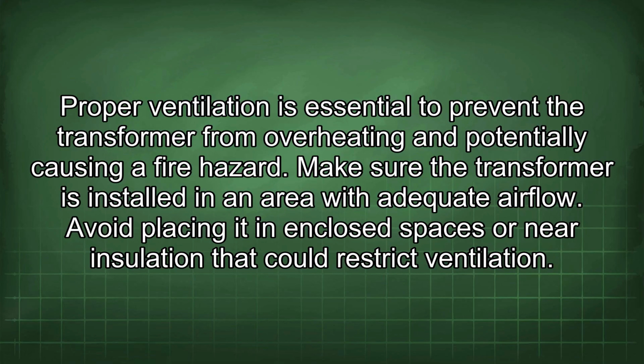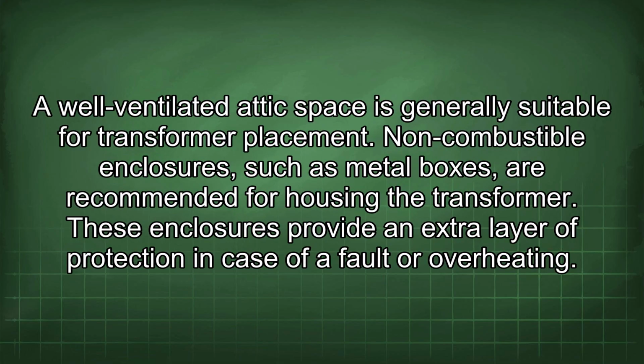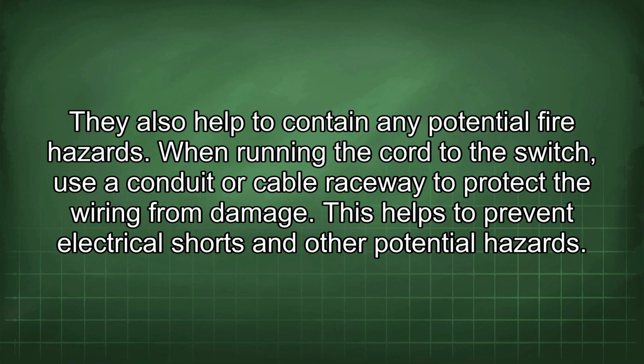Make sure the transformer is installed in an area with adequate airflow. Avoid placing it in enclosed spaces or near insulation that could restrict ventilation. A well-ventilated attic space is generally suitable for transformer placement. Non-combustible enclosures, such as metal boxes, are recommended for housing the transformer. These enclosures provide an extra layer of protection in case of a fault or overheating. They also help to contain any potential fire hazards.